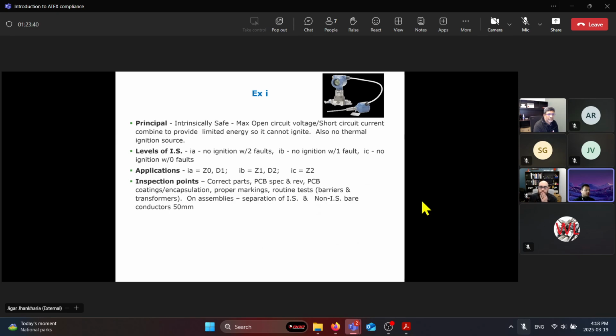So, just to quickly go over intrinsic safety: maximum open circuit voltage or short circuit current combined to provide limited energy, so it cannot ignite. So something, Luke, that you touched on. And there should be no thermal ignition source. When we do testing for intrinsic safety, there are 3 levels we can do this to. If you would like the product certified for zone 0, then we would test your product for no ignition with 2 countable faults.